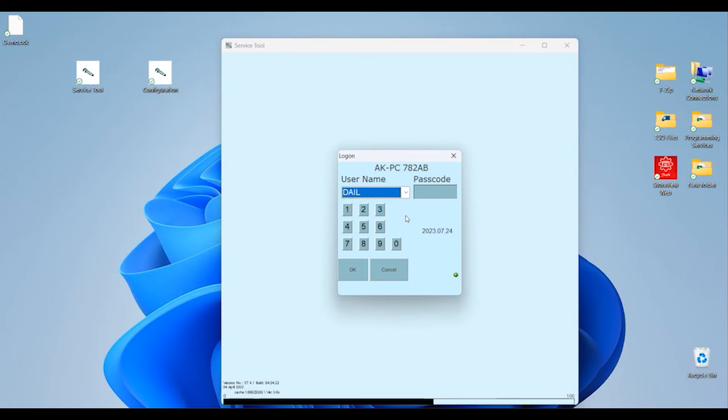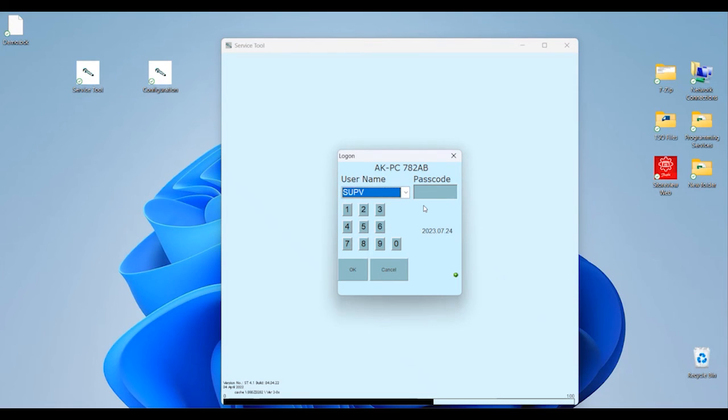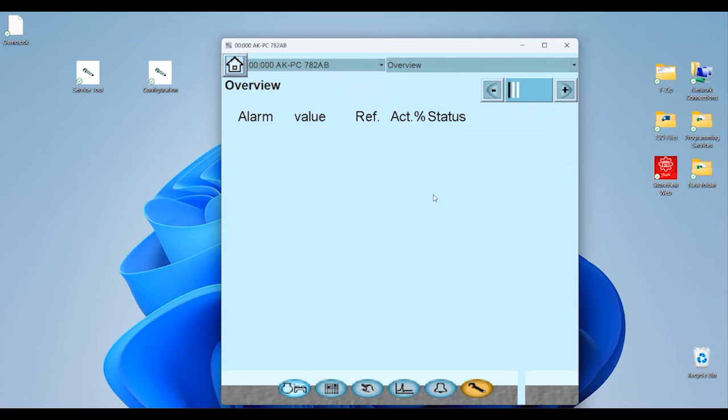Once we're brought into the login screen here, defaults for service tool for a pack controller would be to change your drop-down menu to SUPV for supervisor, and then 1-2-3 is the passcode that gets you in.